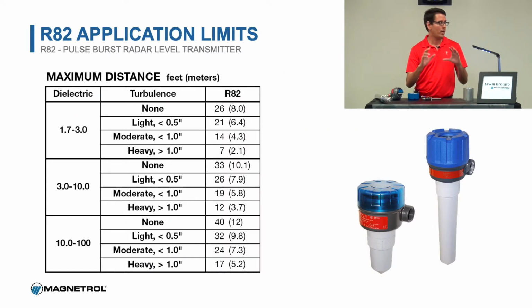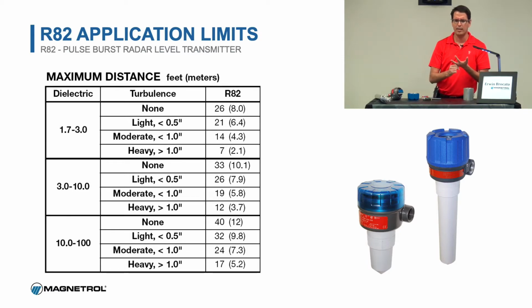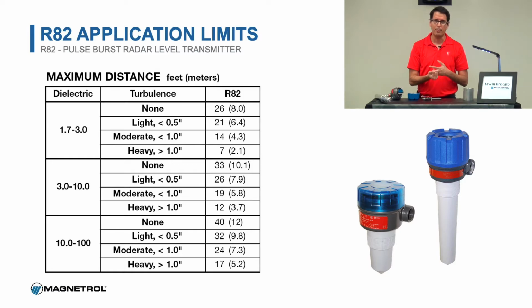Whenever you're talking about radars and setting radars up, you have to consider three main things, which is the distance that you want to shoot through. So if you have a tank that's a certain amount of height, you've got to tell us about that height. You also have to let us know the dielectric constant of the liquid. If you do not know what a dielectric is, or if you do not know the dielectric of the liquid, you can just Google. Most of these are online already. And of course, the disturbances in the process. So if you have any kind of agitation, if you've got agitators, if you've got foaming in the process or rapid movement up and down in the tank, that's something that we need to know to set up the device correctly whenever we're installing it.